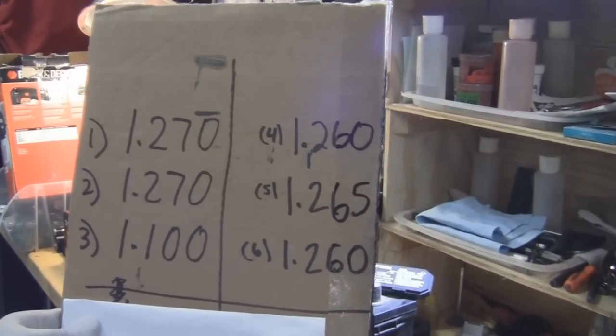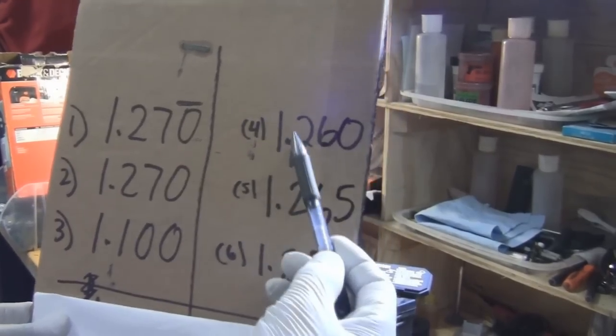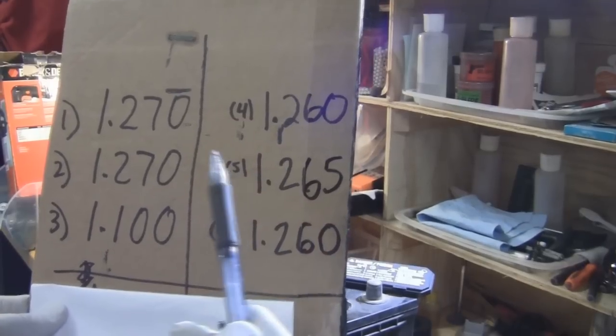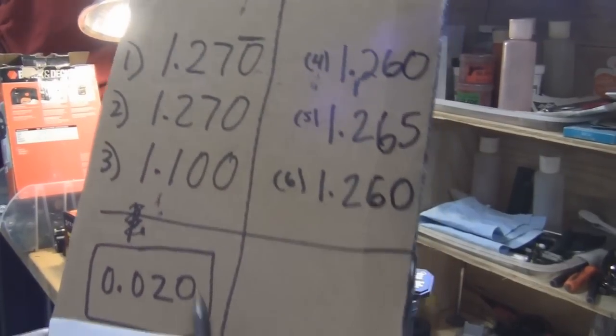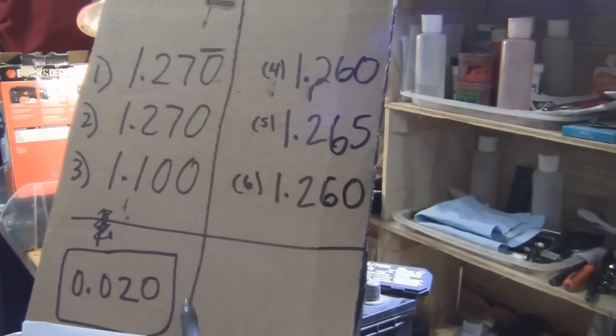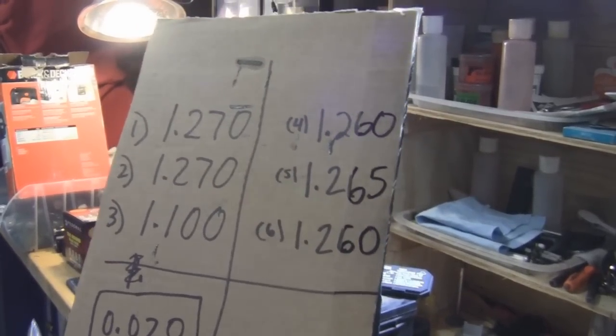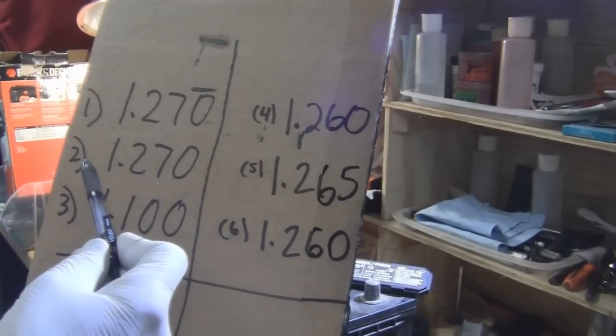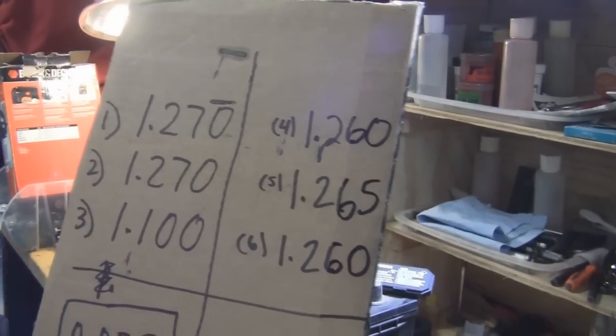After measuring all the cells: cell 1 was 1.270, cell 2 was 1.270, cell 3 was 1.110 and 1.100, cell 4 was 1.260, and cells 5 and 6 were 1.260 and 1.265. So what's the magic number? If you take your highest cell and your lowest cell and the difference between them is more than 0.020, the low one is your bad cell. A bad cell means the battery is defective and you need to get a new one. In this case, with a high of 1.270, any cell below 1.250 is a bad cell.